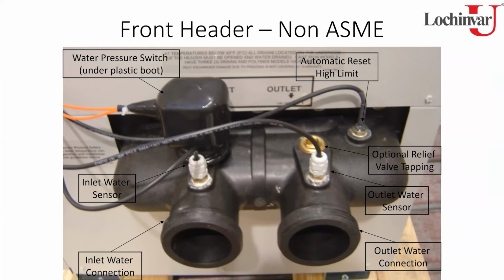The reason for that is we're going to superheat that water really hot, and that is to prevent condensation. You get those flue gases out of that dew point range by putting so much heat into the water. Now, we're going to superheat that water, so that means I've got to cool it down on the other side. That's why I'm diverting or bypassing that water from the inlet to the outlet.